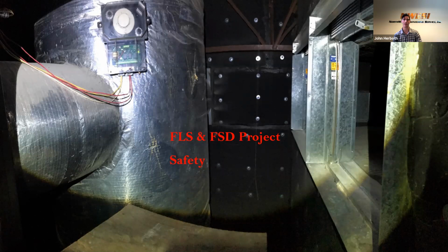25 to 50 dampers in one day for fusible links that are one-handed. So if anybody has questions about project safety, feel free to let me know, because you're going to be in situations where you've got to keep your guys rested and make sure they have a sustainable pace, because it's really hard. You can estimate it takes about 10 to 15 minutes for a fire smoke damper, but it could take up to 45 minutes for one fusible link if it's in a hairy situation. It's really hard to quote those types of projects, and that's why setting expectations is so critical.